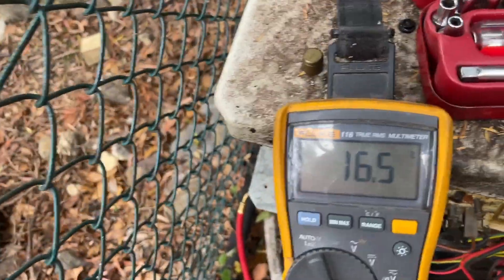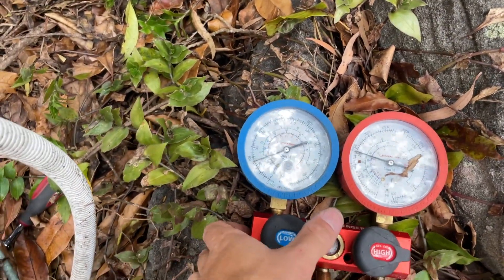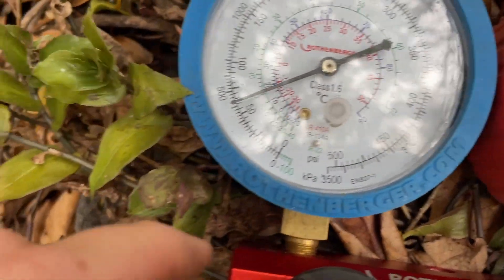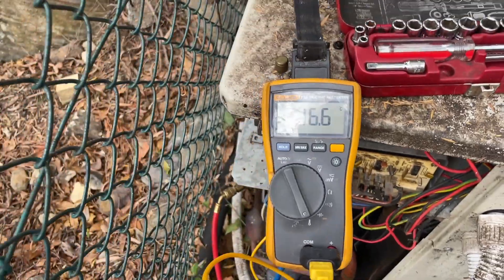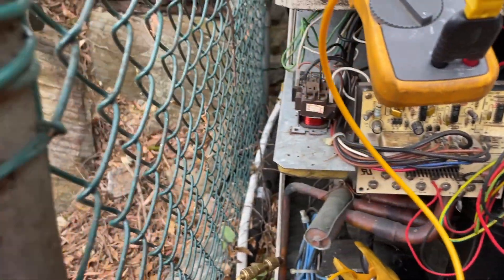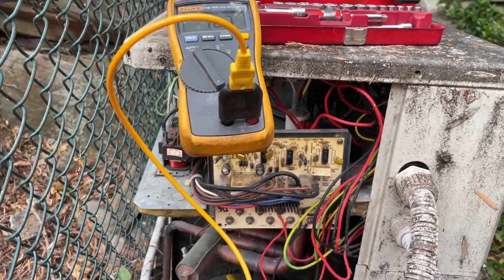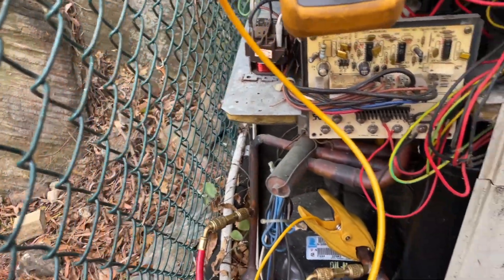Alright, so we have got 16.5 degrees Celsius on the suction line, just over 400 kPa on the suction pressure — that's about 0, about 10... you can see 22 and 0, the difference is 16 — so this thing is short on gas. But I cannot tell me that modern inverter air conditioners are better for the environment: this thing is 30 years old and still running. Compressor's running, outdoor fan's running, indoor fan's running.